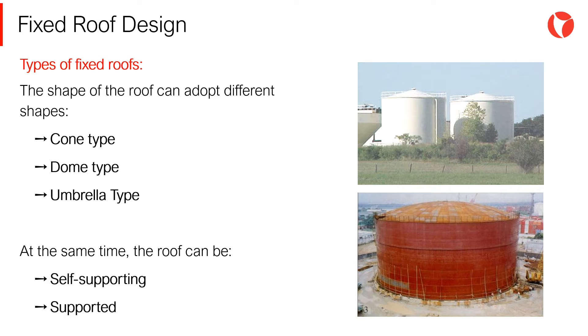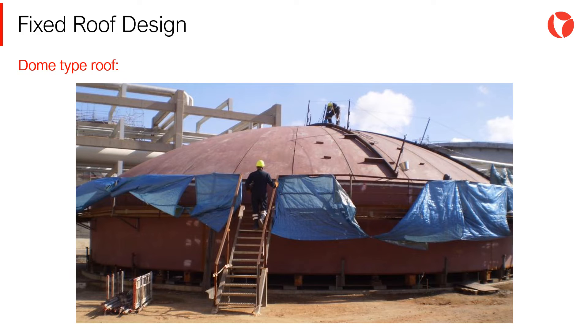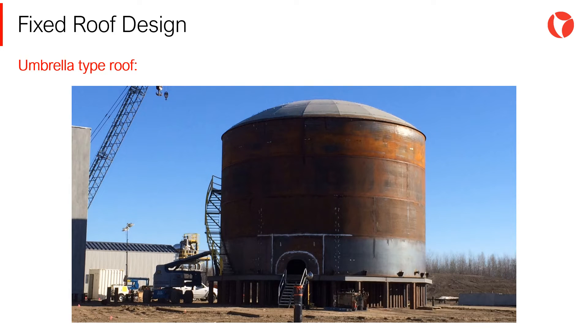At the same time, the roof can be self-supporting or supported. Conical roofs are characterized by their easy construction, with a cover in the shape and surface of a straight cone. Dome type roofs are less used than conical roofs because of the complex and difficult manufacturing process, as each sheet and segment must conform to the radius of curvature of the roof, increasing cost and delivery time. Umbrella type roofs are a variety of the dome type, which only keeps the curvature on the vertical axis.